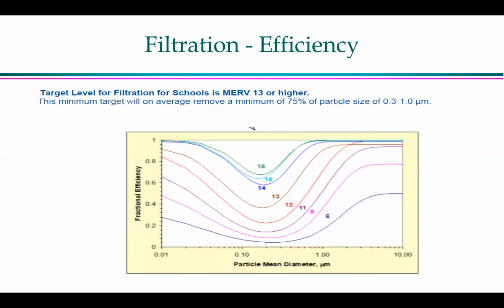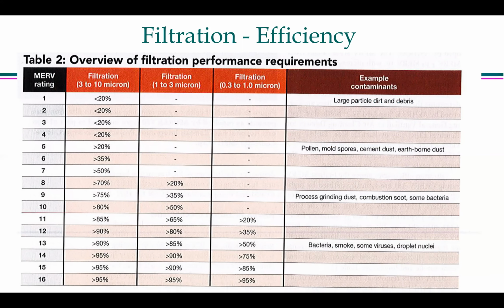So this shows you, and I might spend a lot of time on that, the various filter levels. But you also need to keep track of the fact that the MERV ratings only go up so far. They only go up to 16, but some people are saying they have 17, 18, 19 MERV. The national ASHRAE standard for testing of filters, 52.2, doesn't go above 16. So be careful if you get into the high efficiency filters. So next. This is a summary area for microns. You can see that until you get to MERV 8, you're not going to get down to anything less than 3 microns. So you're still going to have fine dust. When you get all the way down to 16, you can get some pretty good filtration. But keep in mind that the viruses are about 0.1 micron to 0.2 microns, so you're still not going to catch those. So I think we can go to the next one.